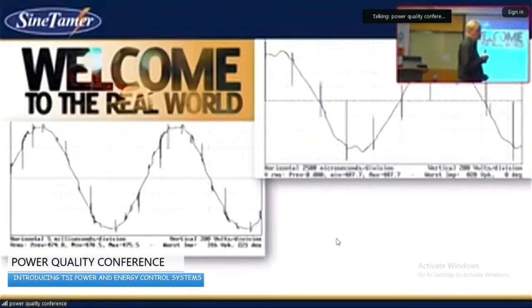This is what you're generally going to find if you start doing an analysis of it. Typically, with any kind of surge protection device, you're going to have a positive voltage and a negative voltage where the MOV actually triggers. So if it gets an over voltage spike, like a lightning strike, that's when the MOV activates. But what it's not doing is catching all the little transient events which happen on the sine wave. It's only clipping positive and negative, not all the way along the sine wave.